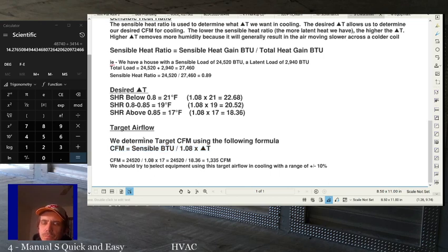So, for instance, a sensible load of 24,520, right? Same one we used up here, divided by 1.08 times 17. 1.08 times 17 is 18.36. So 24,520 divided by 18.36 gives us 1,335 CFM. So equipment that has a sensible load of 24,000 BTUs in a place probably like Arizona or something is what this would be: 1,335 CFM.